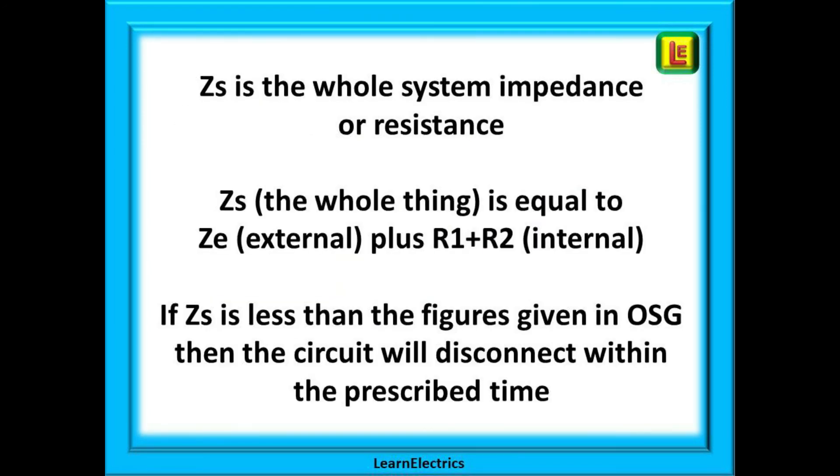To sum up, ZS is the whole system impedance. It is made up of two parts: ZE, the part that is external to the installation, and R1 plus R2, the internal part of the installation. ZS, the whole thing, is equal to ZE, the external part, plus R1 plus R2, the internal part.